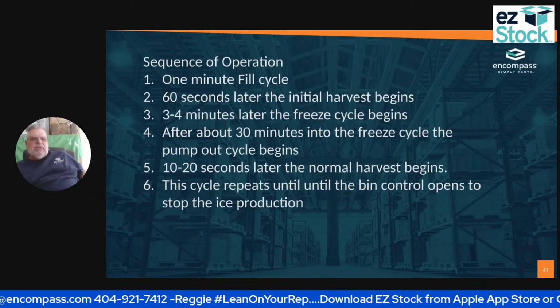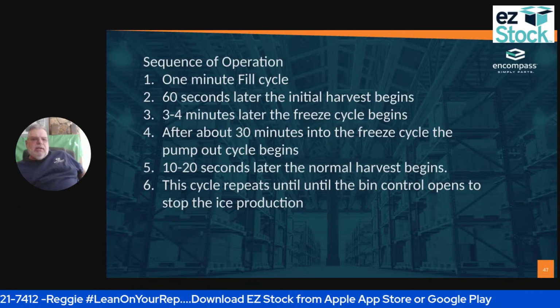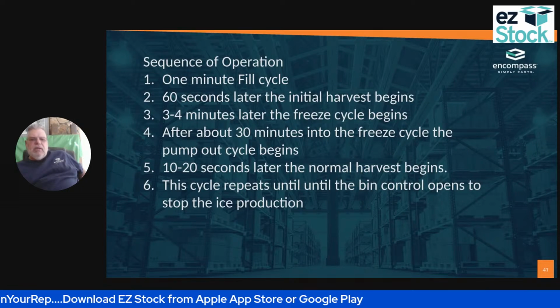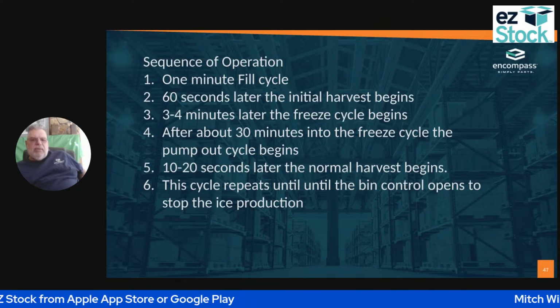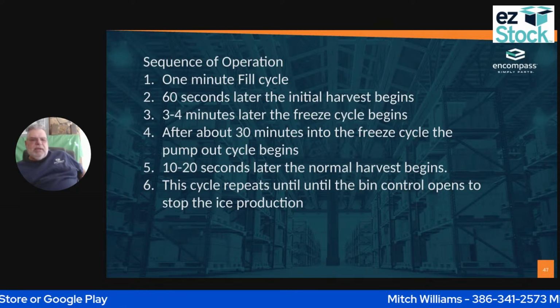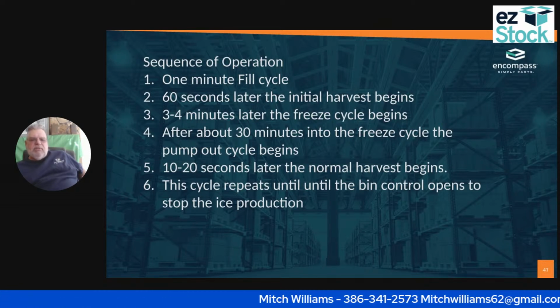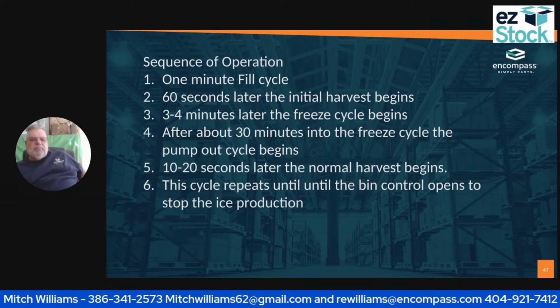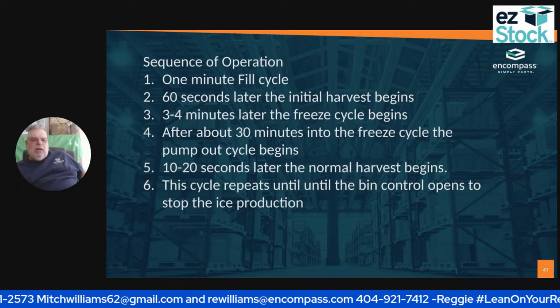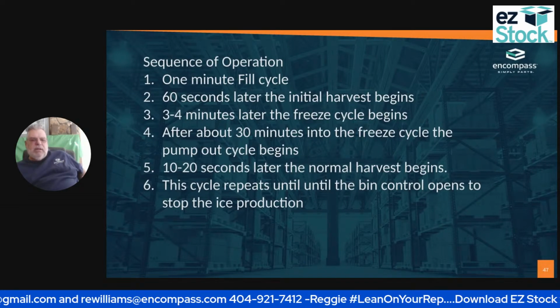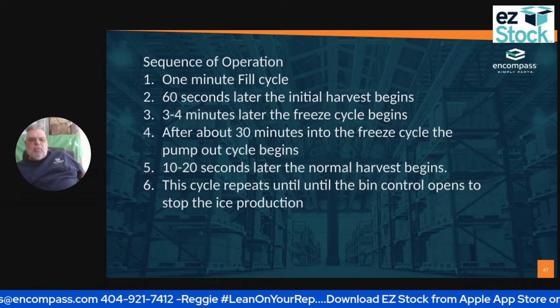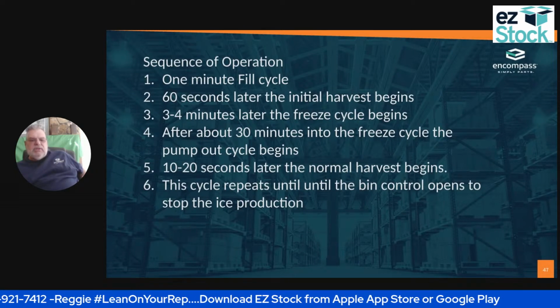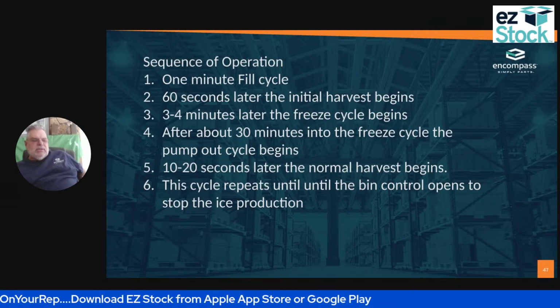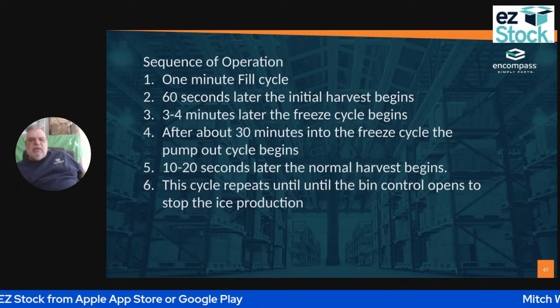So the sequence of your operation right here: there is a 1 minute fill cycle, then it goes to a 60-second period after the initial harvest begins. I get 3 to 4 minutes in the freeze cycle. After about 30 minutes into the freeze cycle, the pump starts cycling.